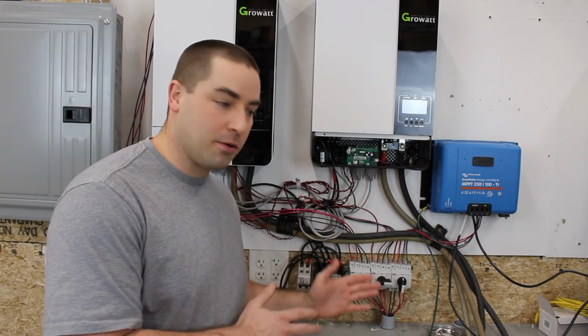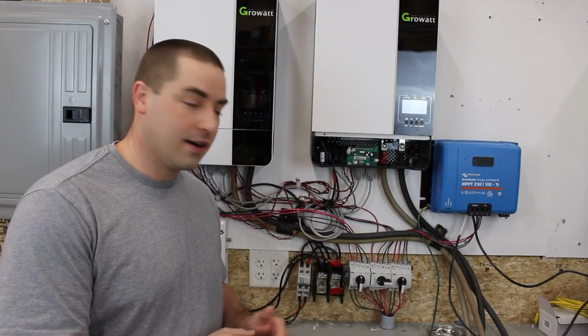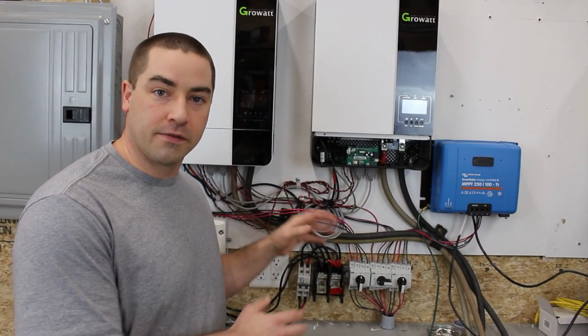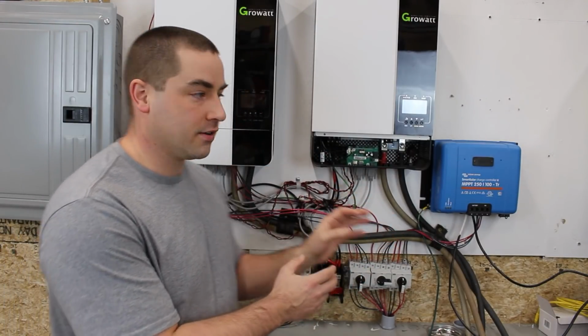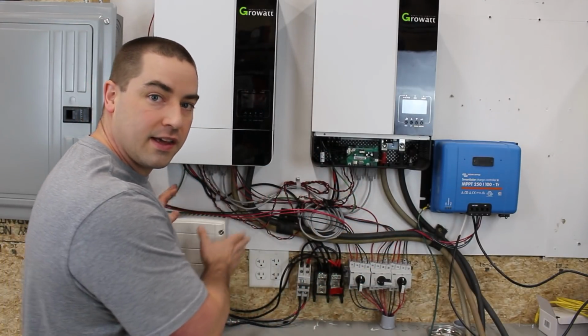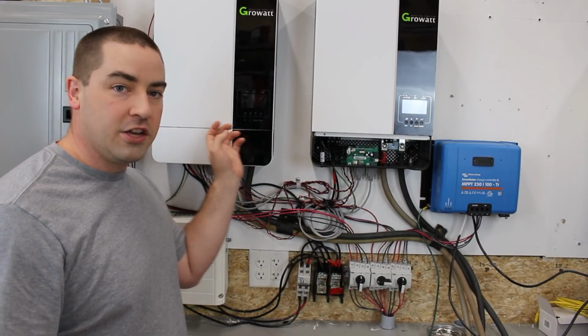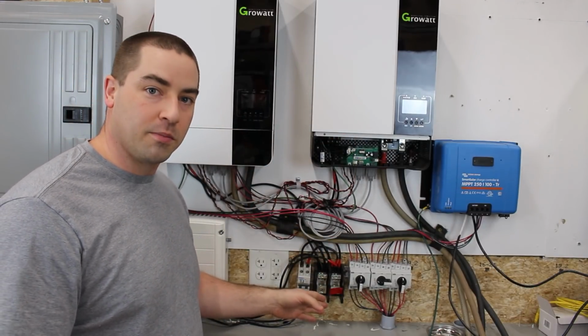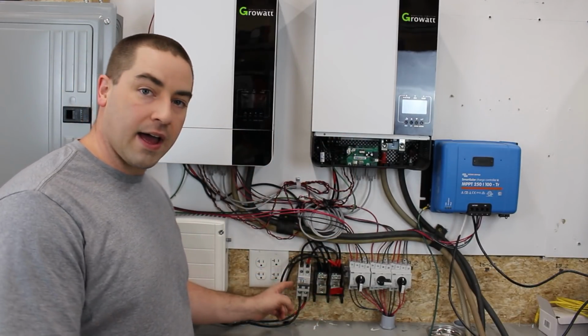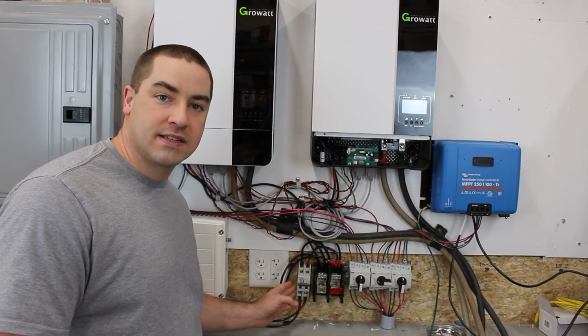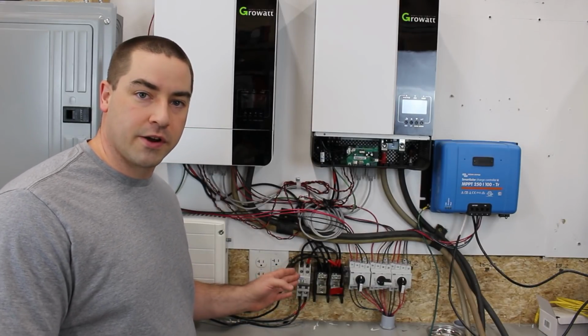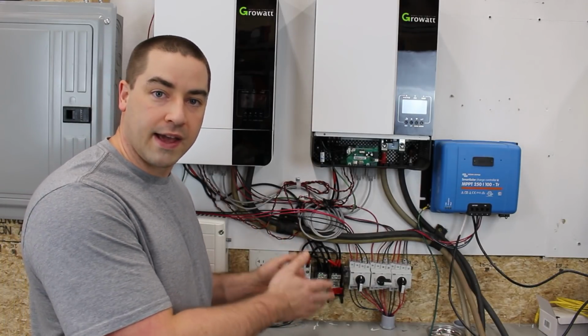So what I did in the meantime is I wired in a terminal block. So that's right here. This black terminal block is a way that I can wire all of these things hardwired in. So right now it's hardwired into the auto transformer. Each inverter is hardwired to the terminal block. And then I have one output. This is a 63 amp double pole circuit breaker which breaks both L1 and L2, which feeds the circuit breaker box.